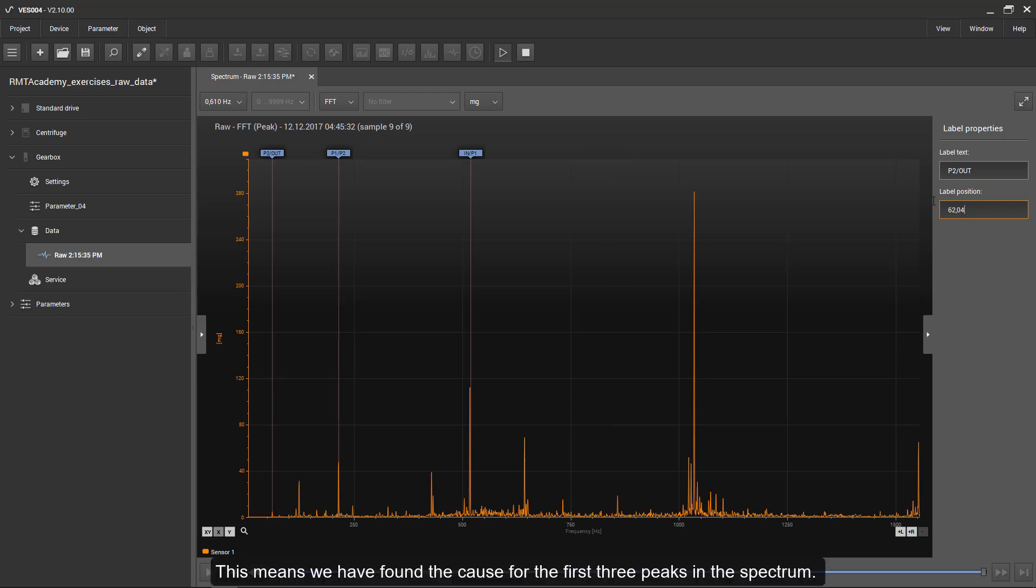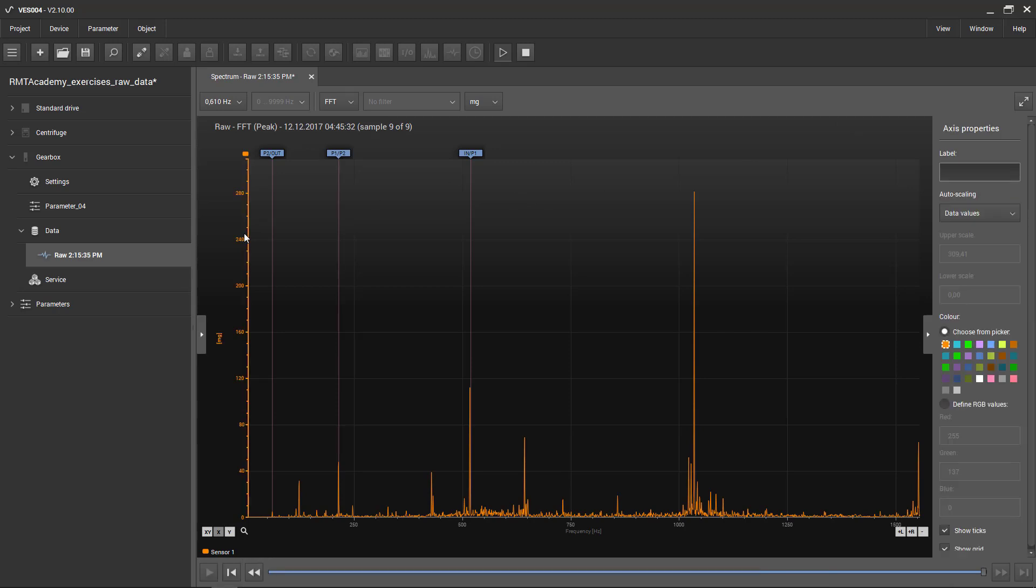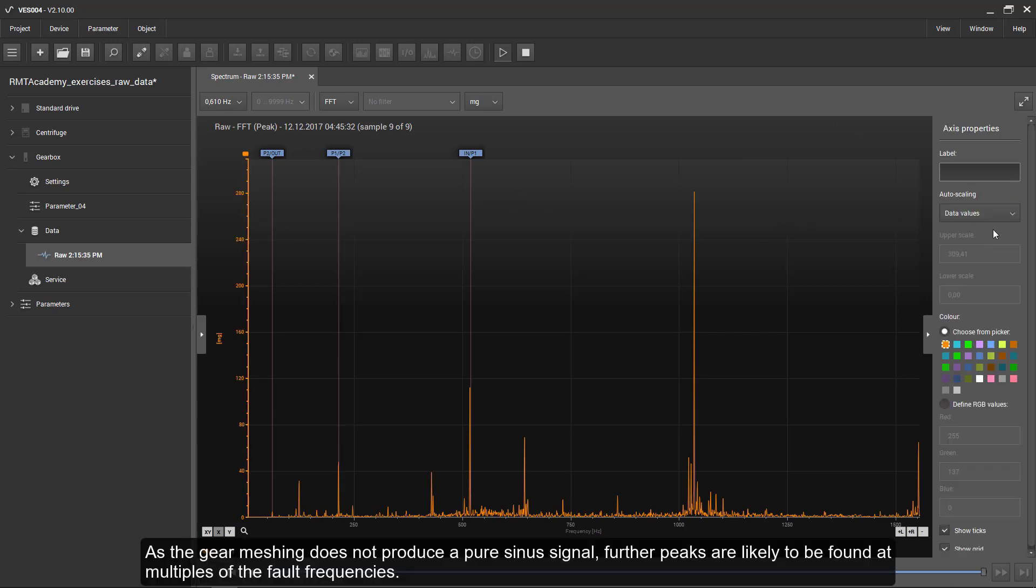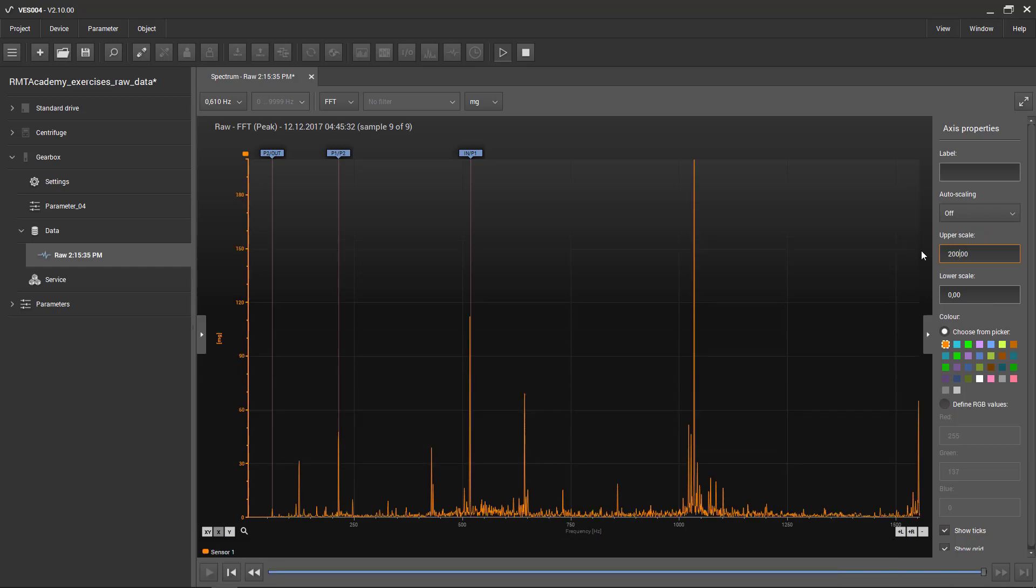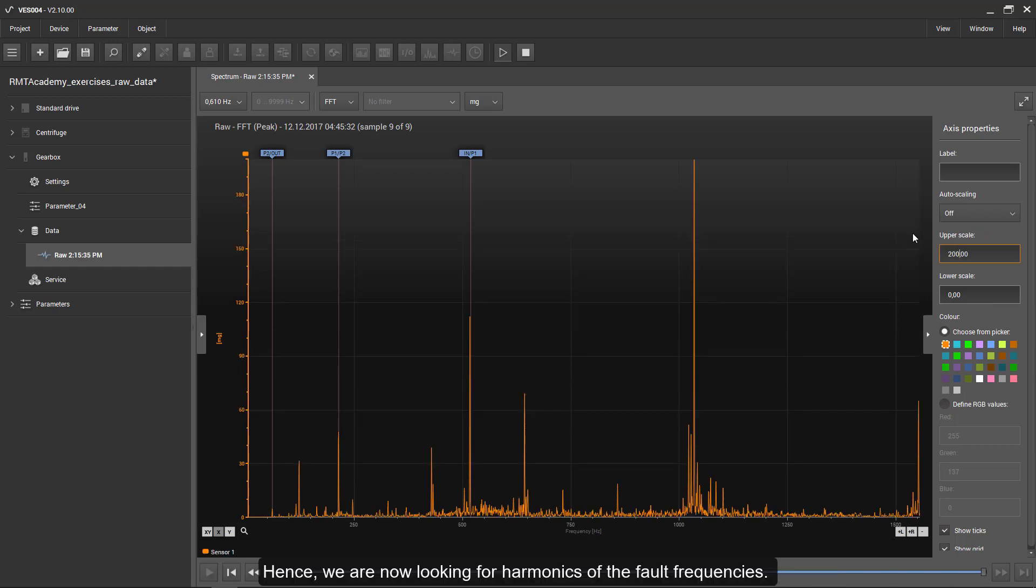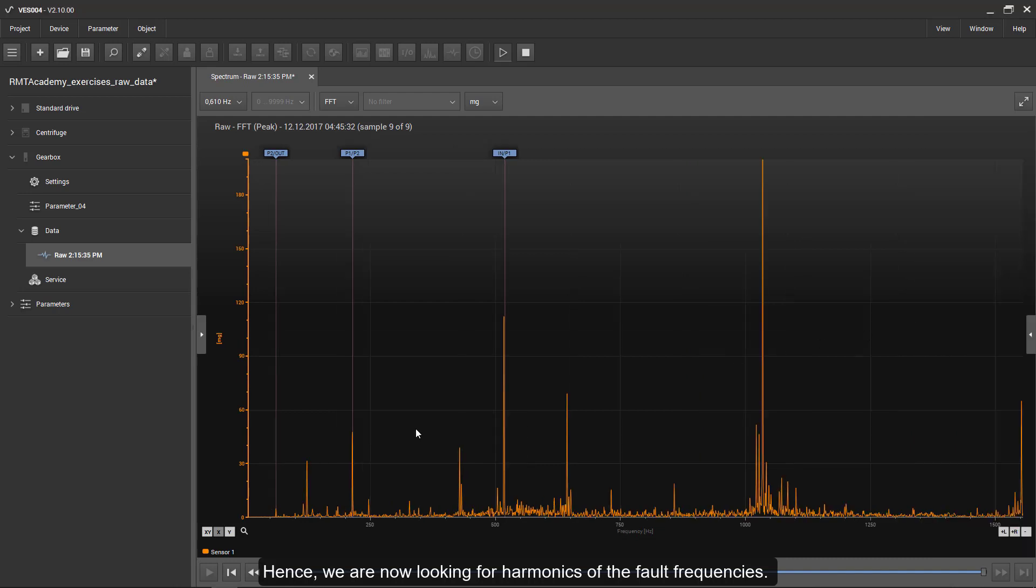This means we have found the cause for the first three peaks in the spectrum. As the gear meshing does not produce a pure sinus signal, further peaks are likely to be found at multiples of the fault frequencies. Hence, we are now looking for harmonics of the fault frequencies.